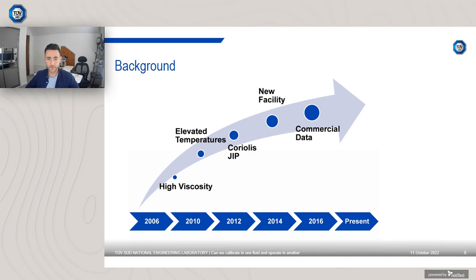There was always a question around elevated temperatures, especially with respect to Coriolis meters. And in 2010, some customers who were looking at a new field in the North Sea, or an upgrade to a facility, it was operating at high temperature, previously used turbine meters, and they were switching them out to Coriolis meters, but they were operating up at 70 degrees Celsius. And they wanted to know whether elevated temperature affected the performance of Coriolis meters. So we did some initial trials in our facility up to 60 degrees, because that's the maximum temperature we could achieve at that time. And we found that there was a slight temperature effect, not as large as viscosity, but certainly an effect nonetheless.